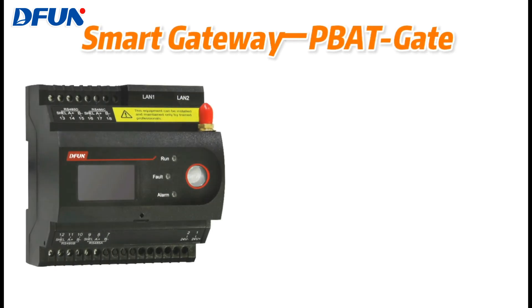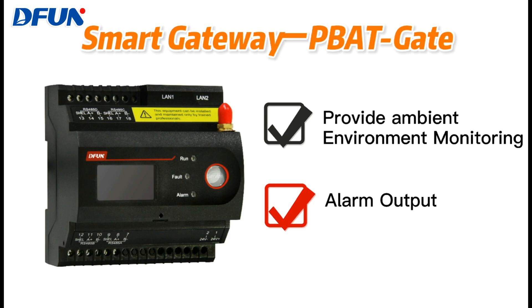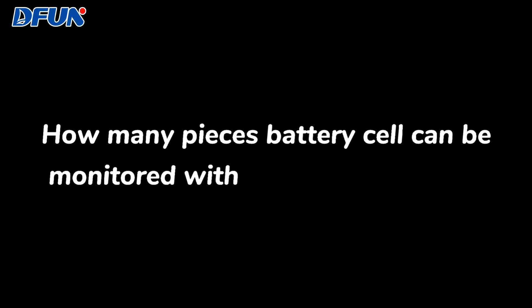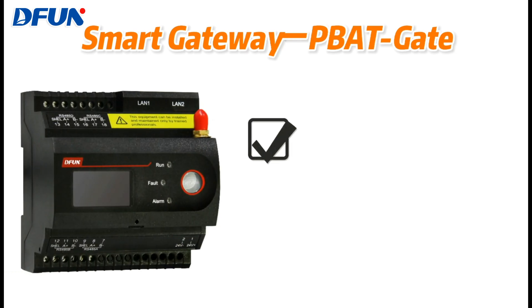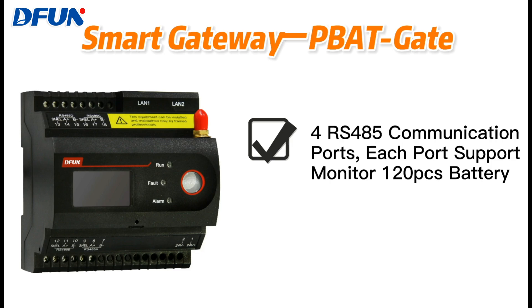Can this gateway provide any environment monitoring also? Yes. This gateway provides two analog inputs for ambient environment monitoring and one digital output joint contact for alarm output. As we equip 4 RS485 communication ports with the gateway, and each port can support monitoring 120 pieces of battery cells, so one PBAT-Gate can support monitoring up to 480 pieces of battery cells in total.